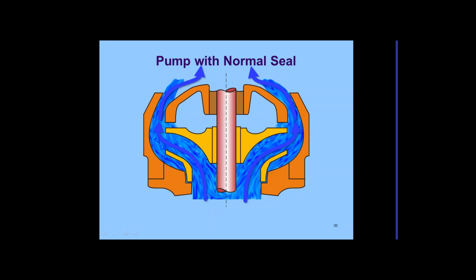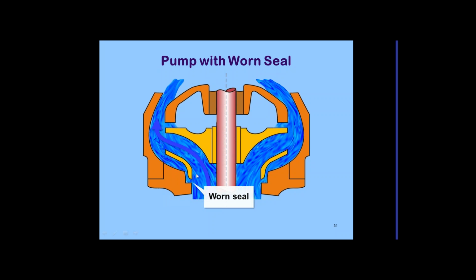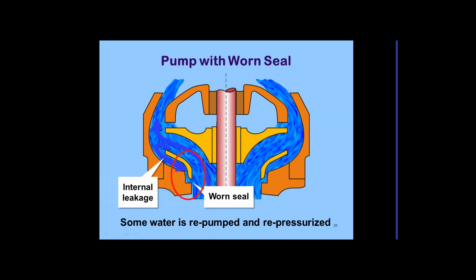So here's a pictorial of how the water is going to run up through here. Typically, this is the spinning part here from a shaft coming down from the motor on top, and you've got a spot right here that's basically a seal surface. And what happens when that wears? These impellers on the bottom thin out, and we get leakage that basically comes around here and leaks through. So sometimes what we can do is just adjust the height of that shaft, and that moves this whole yellow part down closer to the casting or housing to seal this up a little bit to improve the efficiency. So that's a temporary fix, but can save a few bucks in energy costs.